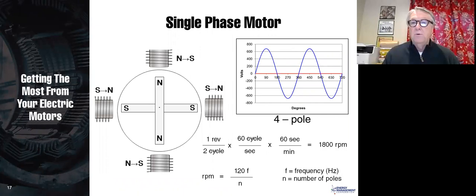Well, it's one revolution every 2 cycles now, because there's a quarter of a cycle, then a quarter of a cycle, a quarter of a cycle, and a quarter of a cycle. So it takes 2 cycles per revolution times 60 cycles per second times 60 seconds per minute, gives us an 1800 RPM motor. And I think you mostly know that a 4-pole motor in the United States runs at 1800 RPM. In Europe, that would be 1500 RPM.